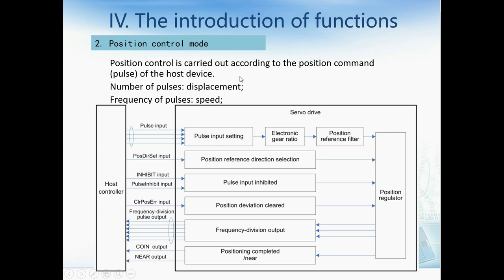There are three control modes of the servo drive: position control mode, speed control mode, and torque control mode. We will talk about position control mode first. Position control mode is carried out according to the position command from the host device, generally from the PLC. The pulse number defines the distance, and the pulse frequency defines the speed.